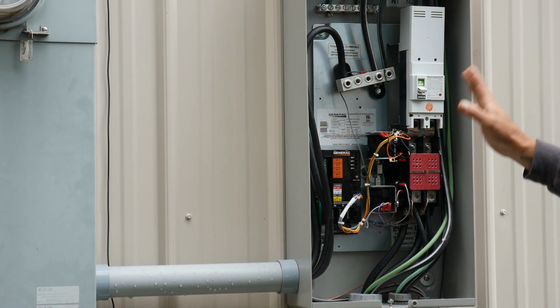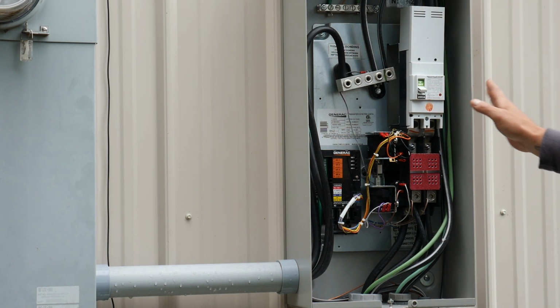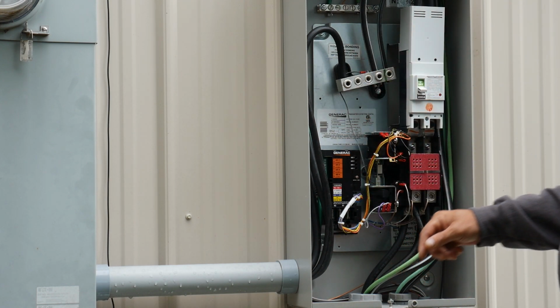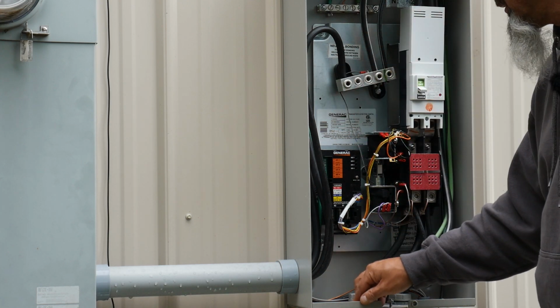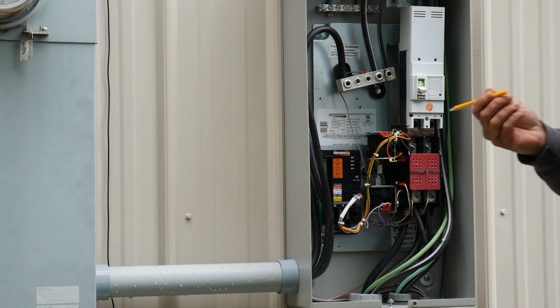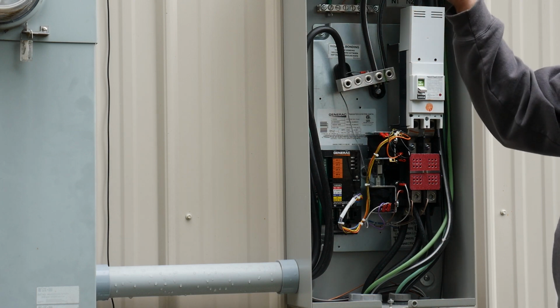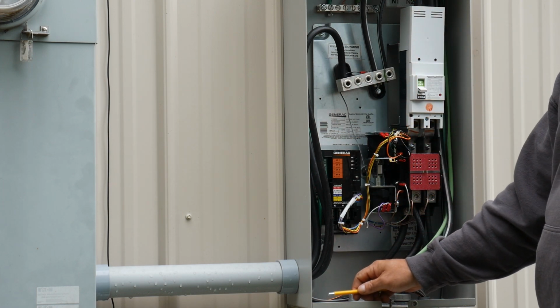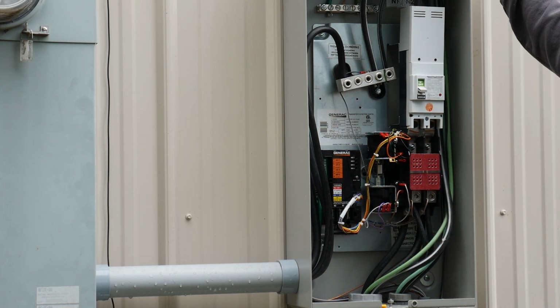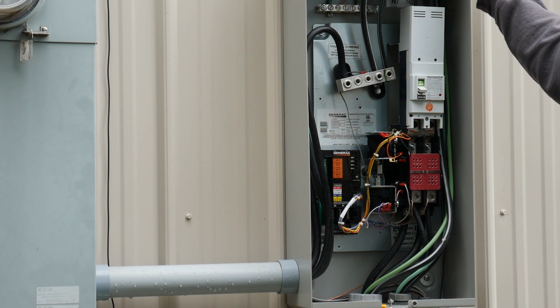But you might come across it where it doesn't have this, and what you'll see is you won't see any of this. All you're going to see is a little box with all these wires, and it's got a little lever. You stick it in there and up or down, depending on what you want. So when you go to check it, make sure it'll be off when you get out there. But when you get ready to do a transfer, you'll want to manually shift it with the generator running, and make sure that you got power in the house.